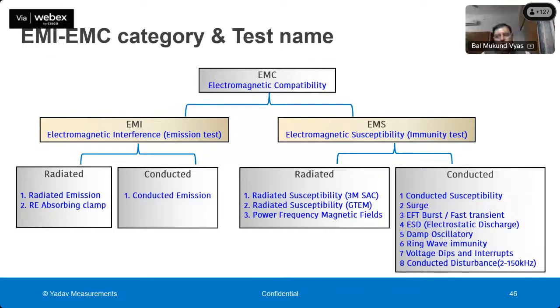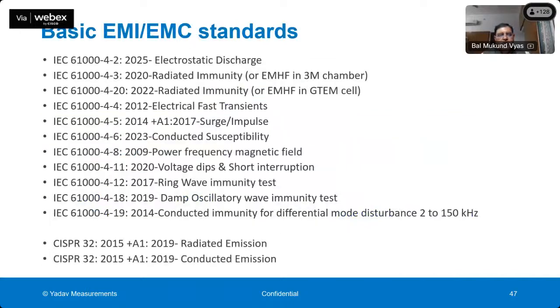When we talk about radiated immunity, there are three types of radiated fields. One is radiated susceptibility, which can be tested in an anechoic chamber or in a GTEM cell, and then there are power frequency magnetic fields. Various types of conducted disturbance can be there: surge, electrical fast transient burst, electrostatic discharge, damped oscillatory wave, ring wave, voltage dips and interruptions, and there can be conducted radio frequency disturbance within 2 kilohertz to 150 kilohertz. As I mentioned, these are the IEC 61000-4 series of standards. These are various standard test methods, and the meter has to pass all these tests as per the IEC 61000-4 series.